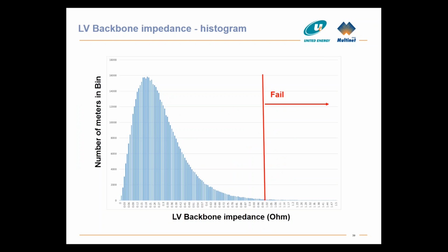What we do with the smart meters is actually use that to measure the impedance back into the network. As a result of these historical deaths, we are forced to inspect each and every property. They use a neutral service tester that just purely does a pass or fail assessment. If the resistance to the house is bigger than 1 ohm, they fail it.